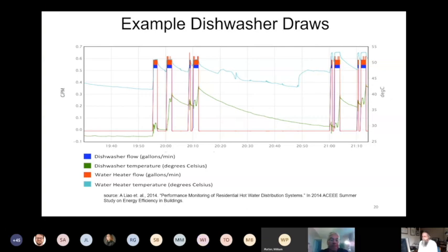The third one, the same. The fourth and fifth, it's cooled off again, so it doesn't get hot water until the sixth and seventh one, or seventh and eighth. So just to notice that the dishwasher is not getting hot water all the time. In fact, hardly ever. Next slide.